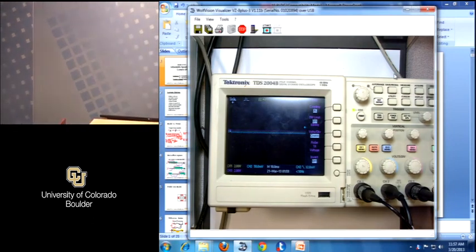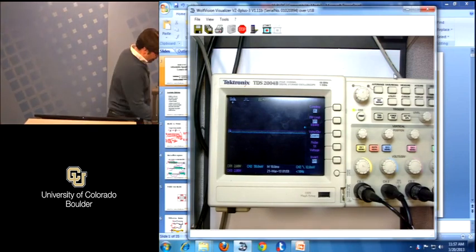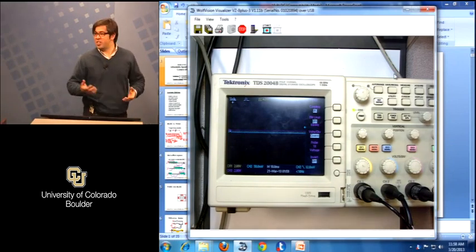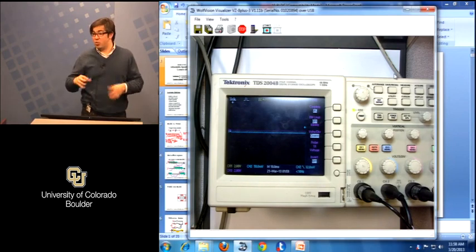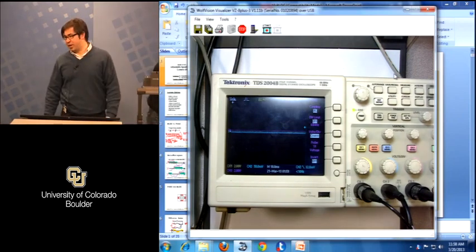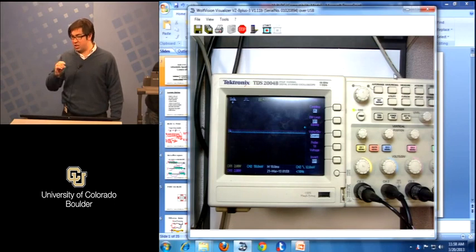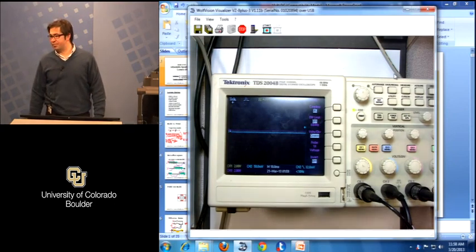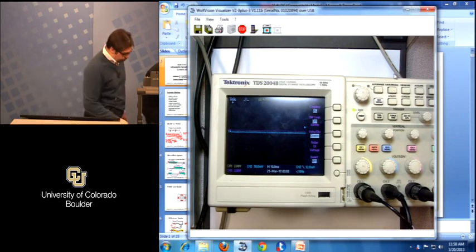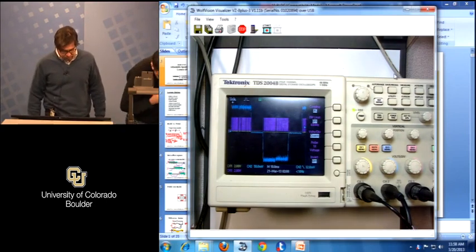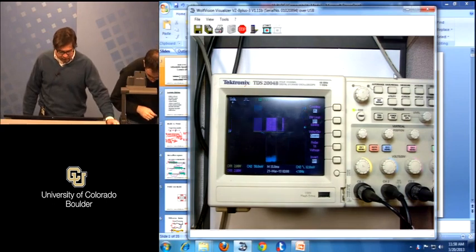So let me help you with that. The third test we want to do here is to load the machine so you really see the phase current being flat and everything loaded, so we generate some torque. So you really see what the hysteresis band is over there, right? And then we're going to change the speed and see if the ripple is higher or lower and see how everything is going on with the drive. You want to keep it like that? Oh, nice. Okay, perfect.